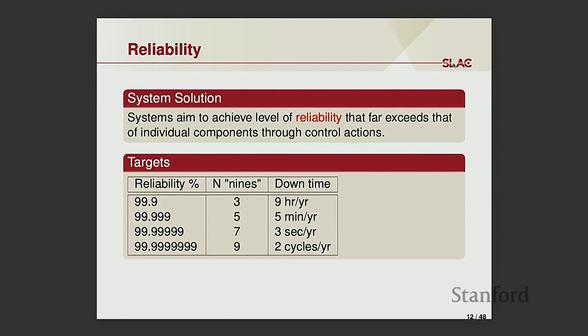Reliability of three nines, meaning 99.9% reliability, means that during a year, which has 8,760 hours, there will be 9 hours of downtime. Well, that's a lot. And for five, seven, and nine nines, five corresponds to 5 minutes a year, seven corresponds to 3 seconds, and nine nines correspond to only 2 cycles, 2 60-hertz cycles being missed in a year.